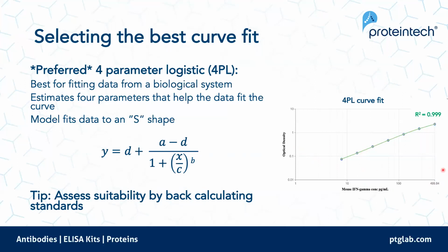And you want to make sure that they're reading really close to the expected values from the curve that you've just generated with them. So that should be around 5 to 10%. If you're not getting that, then do try a different method. There's also something called the 5-parameter logistic, or if you think that a log-log or semi-log plot would be better, that's one way to check here.